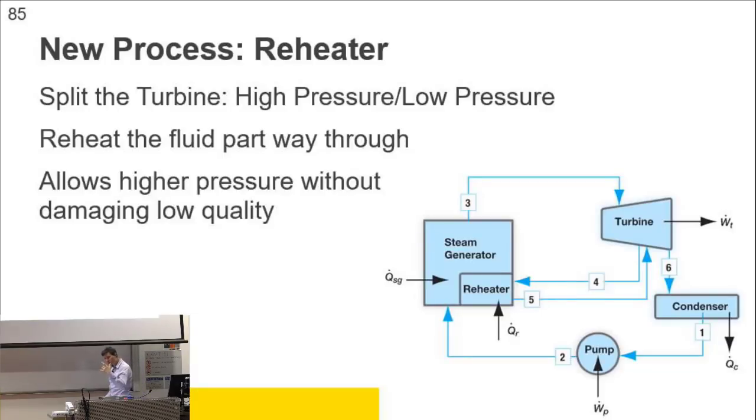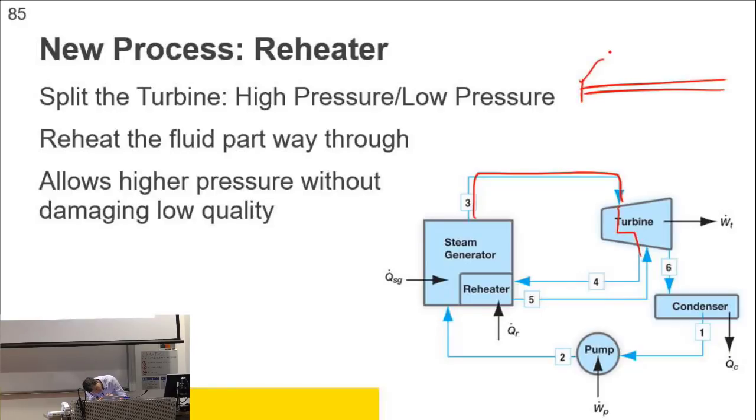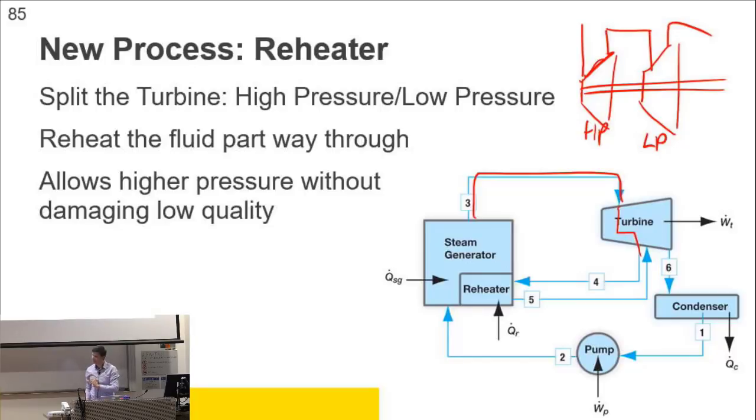Let's talk about introducing another component, some more state points. What does that look like and how can it improve what we're doing? One of the things we can do is, after we come out of our boiler and go into our turbine, rather than just have a turbine with one exit, one mass flow, going all the way through the turbine and out to our condenser, we can go through a portion of a turbine, and these can be two turbines. Sometimes this is drawn with a high pressure turbine and a low pressure turbine. The idea is you'll come into the high pressure turbine, into the low pressure turbine and out.